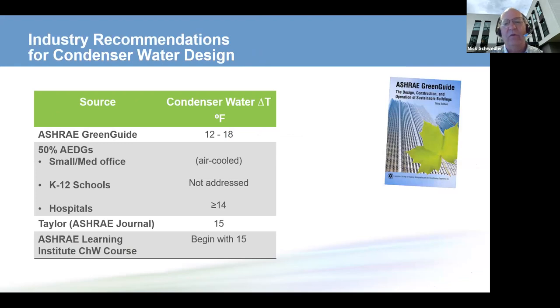Another option is to look at what the industry is telling us. The ASHRAE Green Guide says that rather than the 3 GPM per ton, we should use 12 to 18 degrees delta T on the condenser water side. The Advanced Energy Design Guide for hospitals says a 14 degree delta T, reduce the flow rate. Steve Taylor's ASHRAE Journal article from December of 2011 and the ASHRAE Learning Institute chilled water course say start with at least a 15 degree delta T. That is, reduce the flow rate.